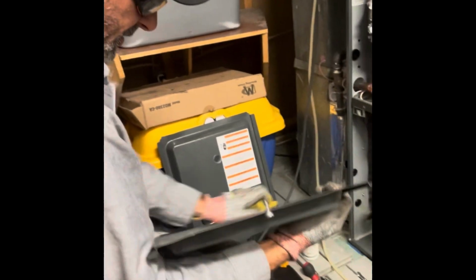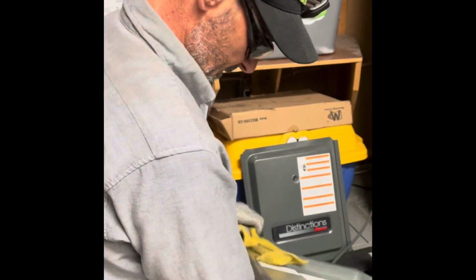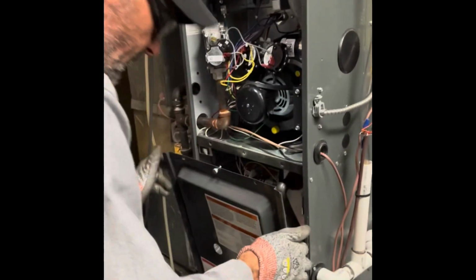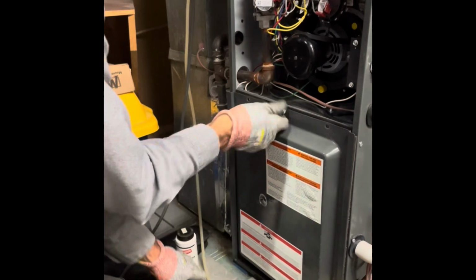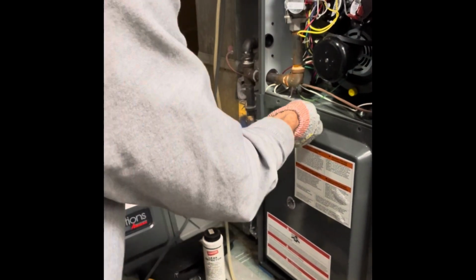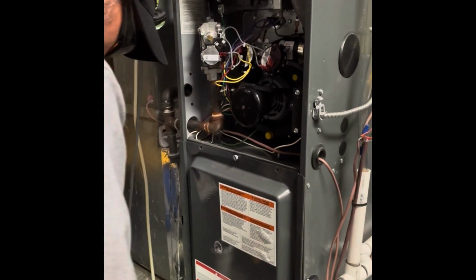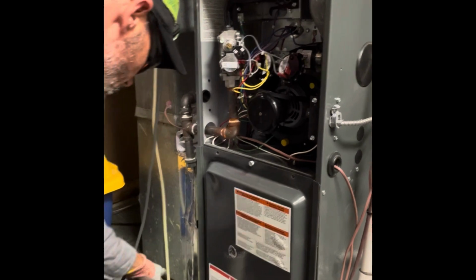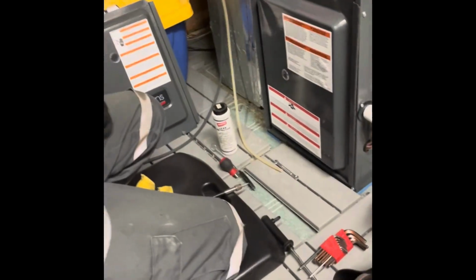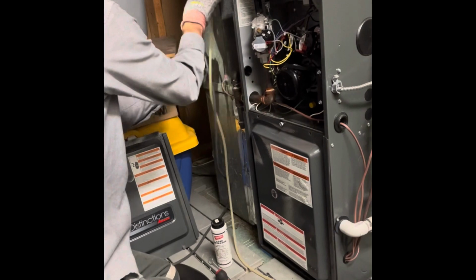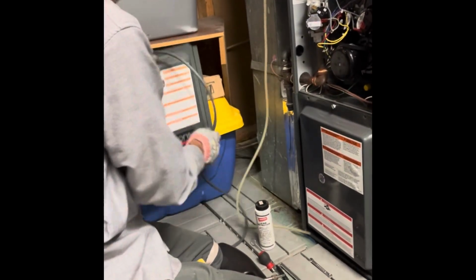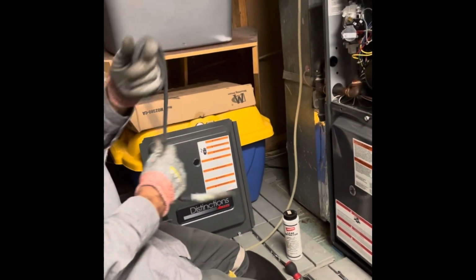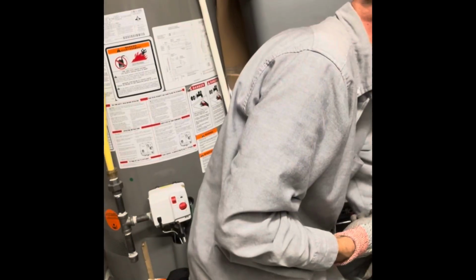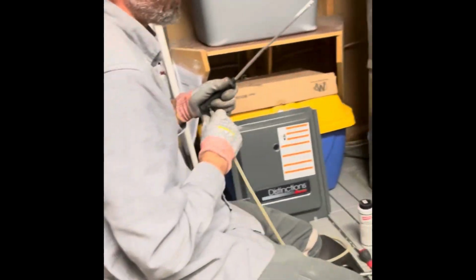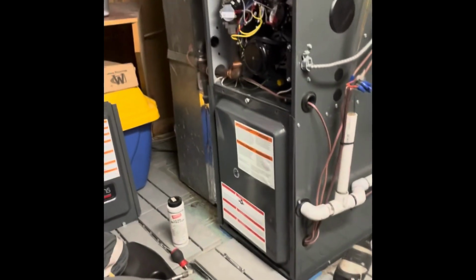So we clean the door, wipe the outside, the inside down, get all the dust off. And we'll put this back on, we'll fire up the furnace, and we'll run a leak test at the valve. So I can start putting all my tools away, because there's nothing else I have to do except for my leak test and put the top door on. So your furnace passed with flying colors. It's doing a great job heating, and the most important to us gas fitters is it's operating safely and keeping the customers safe. So yeah, in a couple minutes this will start up, and then I'll just soap up that fitting. And we'll go upstairs and turn your heat down.